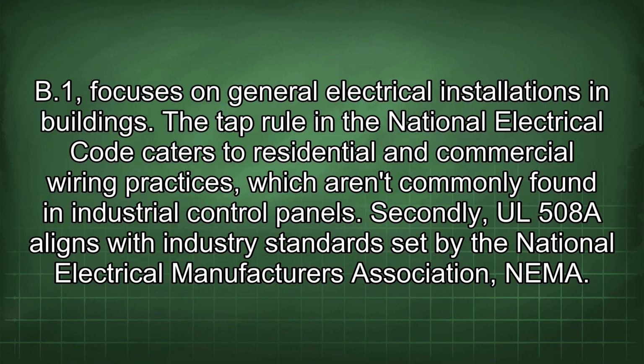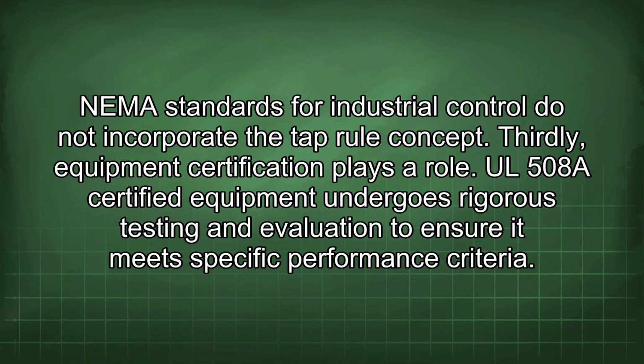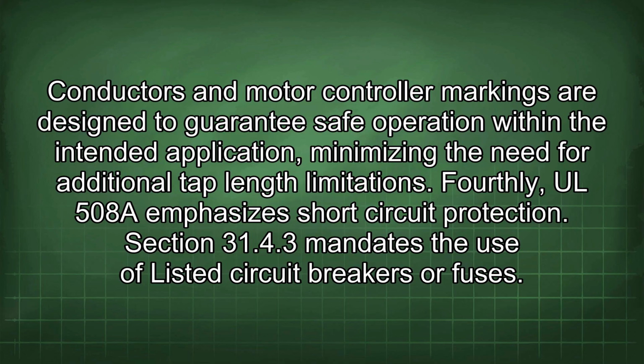Secondly, UL 508A aligns with industry standards set by the National Electrical Manufacturers Association (NEMA). NEMA standards for industrial control do not incorporate the tap rule concept. Thirdly, equipment certification plays a role. UL 508A certified equipment undergoes rigorous testing and evaluation to ensure it meets specific performance criteria.